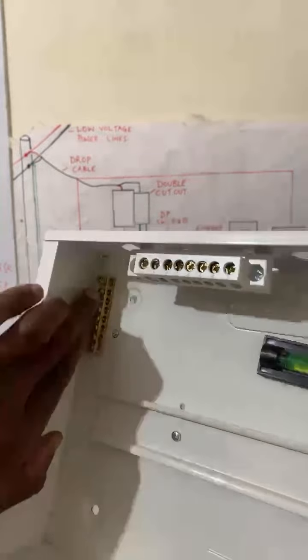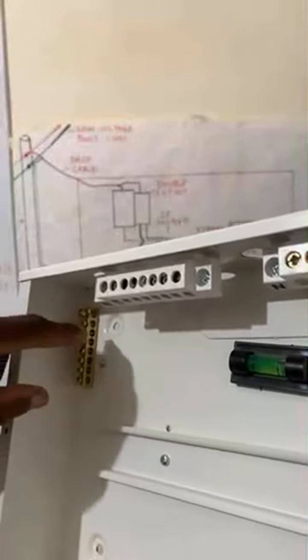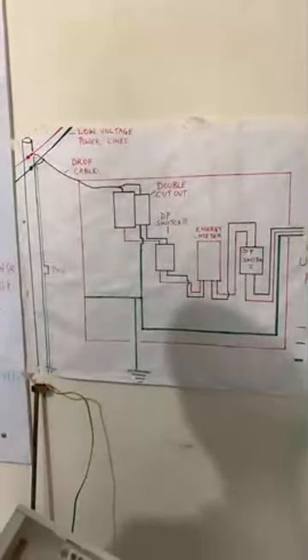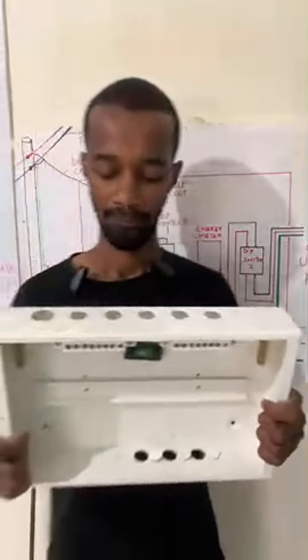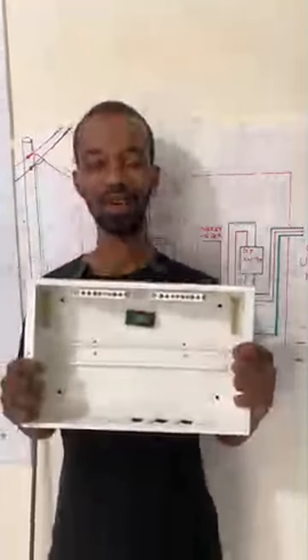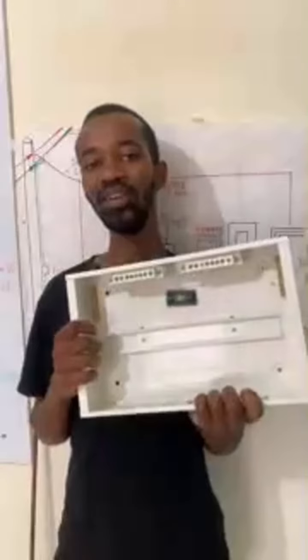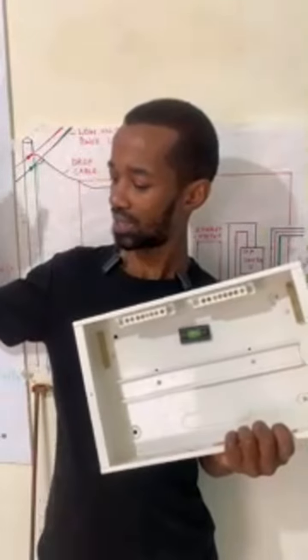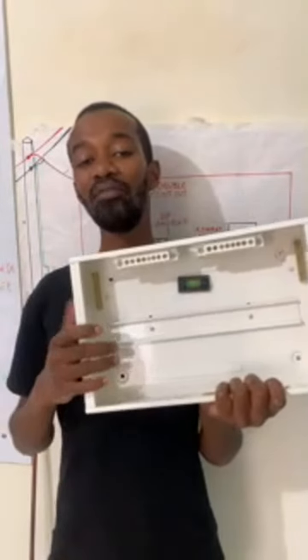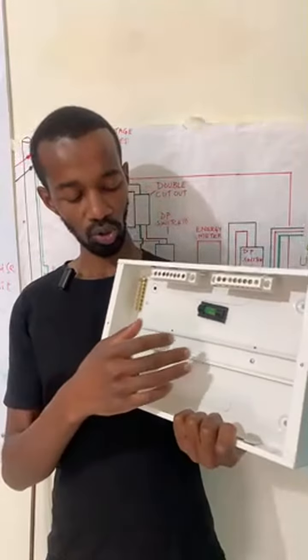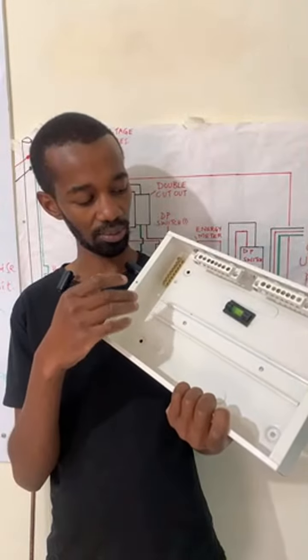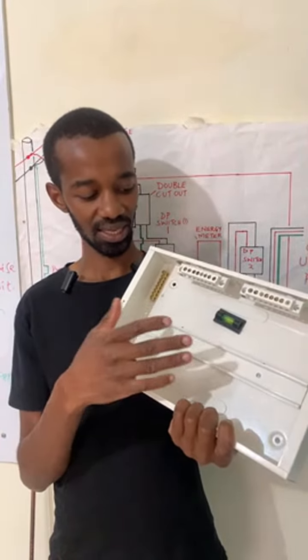So these particular points here for our today's discussion, that we must, for other consumer units that have only one bar, you make sure that the incoming earth connection from the meter box is connected at this point, and then every circuit that goes from that particular consumer unit must be earthed at that point, topmost. So if we are talking about the cooker section or the kitchen section, we have the earthing that is connected here. So I know that I am supposed to have a lot of gadgets here, but for us to elaborate on the point of earthing, I've ensured that there's nothing else in my consumer unit.